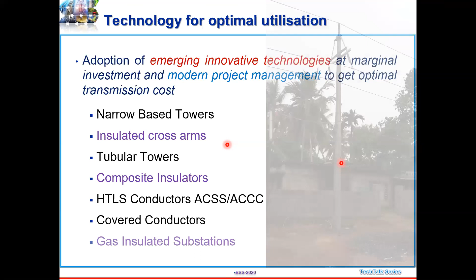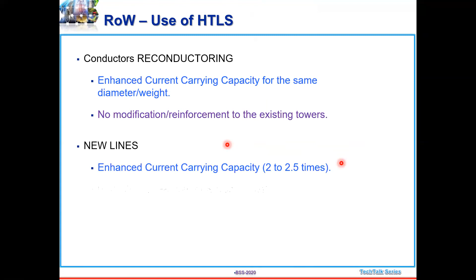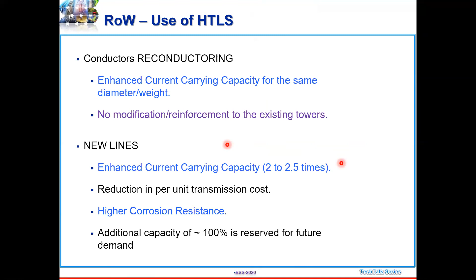So when we are going for reconducting, the main advantage is that the current carrying capacity for the same diameter and weight, as mechanical properties remain the same. No modification or reinforcement is required for the existing tower. You can have around 1.5 times the existing capacity with the reconducting, with the HTLS conductor. And for new right of ways, we can have enhanced capacity 2 to 2.5 times higher, with reduced per unit transmission cost, higher corrosion resistance, and additional capacity.